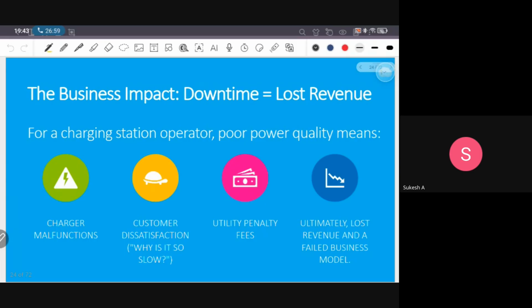We cannot wait till the power system is upgraded to accommodate all these EVs. But poor power quality means chargers will malfunction, because chargers are very sensitive, especially EV charging stations. They are sensing voltage, sensing current, evaluating the power, everything, when connected to the grid. And when something goes wrong or goes beyond the permissible limit, that permissible limit or tolerance is very low. If it goes beyond the limit, it will get disconnected. So charger malfunction and consumer dissatisfaction.